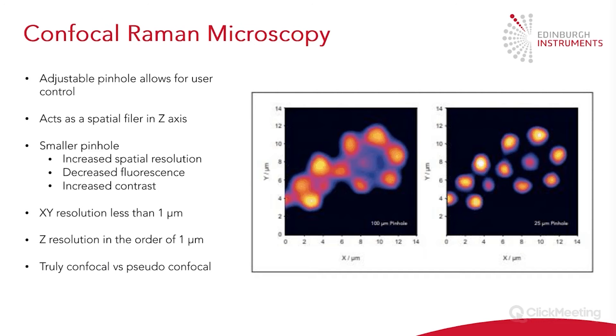We now also have the ability to do Z-resolution, which is typically in the order of one micron. This is because the pinhole acts as a spatial filter in Z by blocking the Raman scatter from above and below the focal plane. A smaller pinhole gives increased spatial resolution, increased image contrast, and also decreased fluorescence. All instruments at Edinburgh Instruments are truly confocal, meaning we have a physical pinhole, whereas pseudo-confocal simulates the effect using the orthogonal arrangement of the entrance slit to the spectrograph and the pixels on the CCD camera. If you want the best resolution, you do need a truly confocal setup.